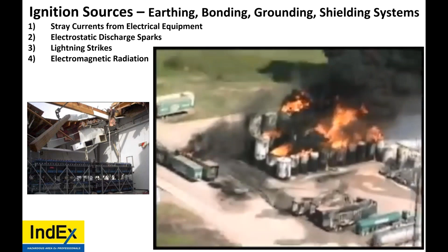And why did this explosion happen? Static sparks. Explosion in Kansas. So, an explosion in a flammable solvent storage tank. They had a level gauge that was a metallic level gauge. Let's just say if your earthing, bonding, and shielding systems are not correct, static electricity will bite.